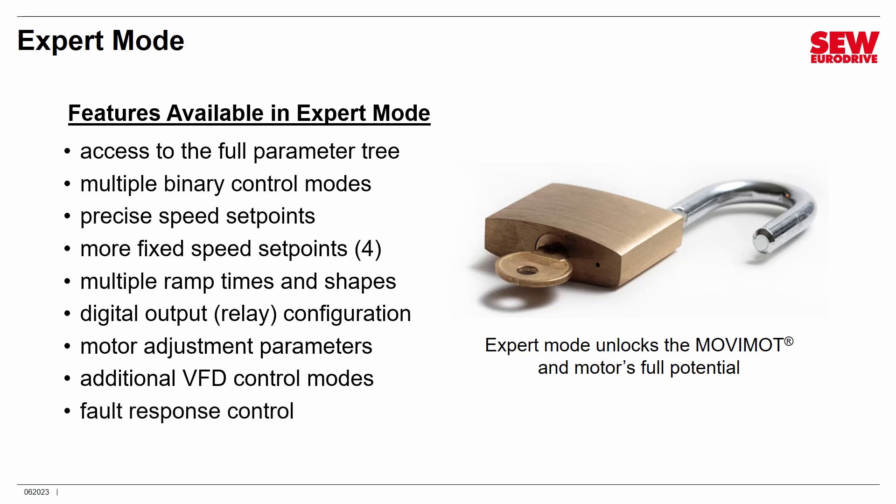There are motor adjustment parameters that allow you to tweak expert motor parameters like magnetization. Most people don't need to tweak those, but they're only available in Expert Mode. There are also additional VFD control modes beyond just VFC and VF, which we'll explore briefly. Finally, you can control how the Movimot handles fault situations. In Easy Mode there's a default fault handling, but you can configure the fault response much more deeply in Expert Mode.